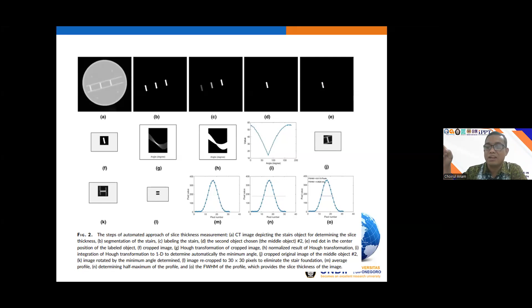across this object, and we can detect the maximum value and minimum value, and eventually we have the full width at half maximum, and then we multiply it with the tangent of the angle of the ramp object, because in the AAPM the angle is 45, so the tangent of 45 is 1. So in the AAPM Phantom, the full width at half maximum directly indicates the slice thickness, because the tangent of 45 is 1.